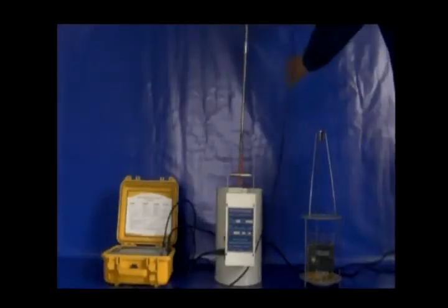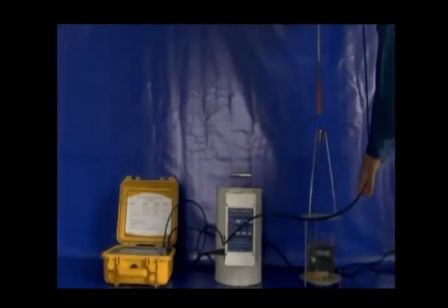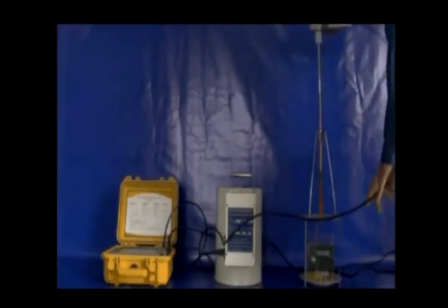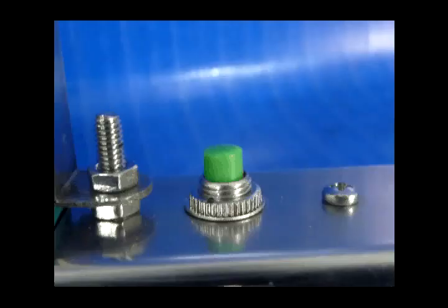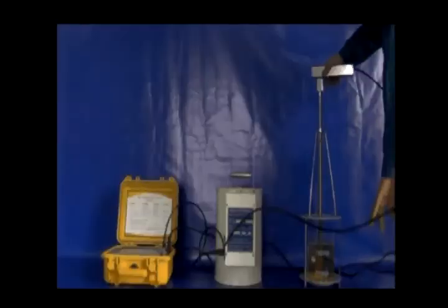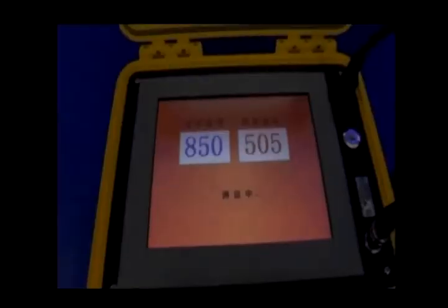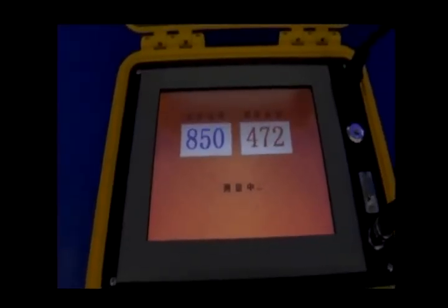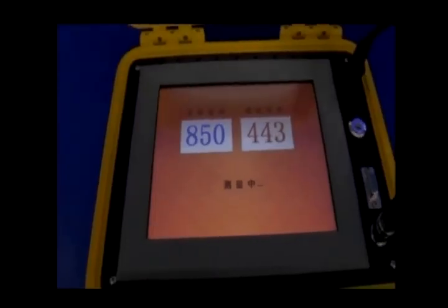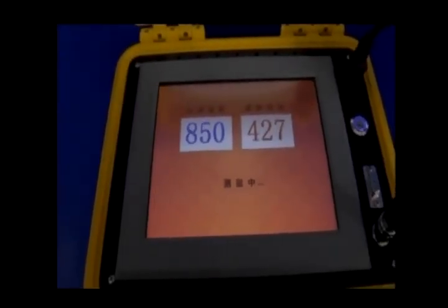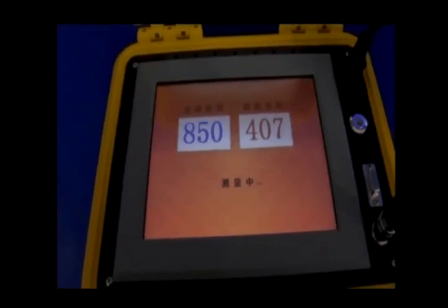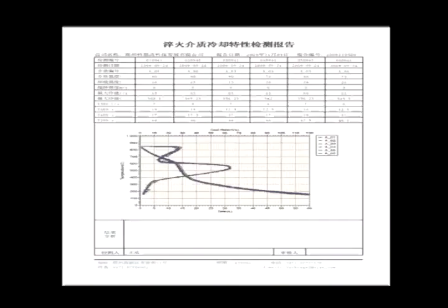Insert the probe vertically into the central hole above the laboratory equipment. At this time, immerse the probe in the medium to be tested. Press the round button on the laboratory equipment one time. Now, the experimental operations are almost complete. Then cool to the temperature which is set before the test. The time is about 60 seconds. Then the recording device will make a long ring. Now the test is completed and the recording device will show the result. You can check the result through it. You can also transfer the data to a computer for managing or printing.